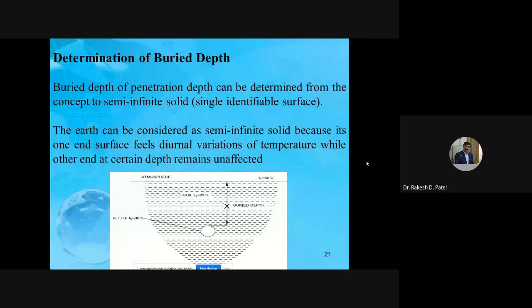Now, determination of the buried depth. The buried depth, or penetration depth, can be determined from the concept of the semi-infinite solid, meaning a single identifiable surface. So from the figure you can easily see what the buried depth is. This buried depth is approximately 3 to 4 meters in the Anand region, and approximately 28 degrees centigrade is the constant temperature throughout the year at this buried depth.